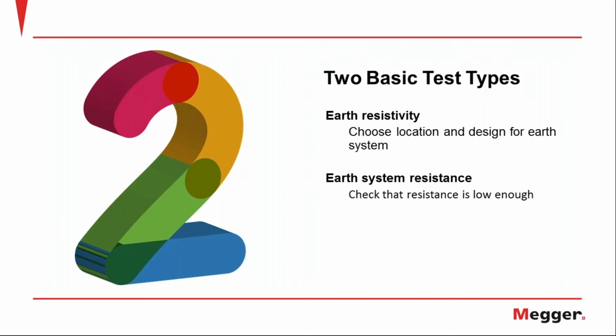Then there's resistance, which is a different function, a different measurement, and a different type of test. Resistance comes in once you've grounded your system and got your ground rod in place - you want to be able to test it. Just driving a rod into the ground isn't enough. It could work if you're lucky, but you don't want to place such high stakes on luck. You want to make sure you actually have a really good ground, and that's where your resistance measurement comes in, which we'll cover as well.